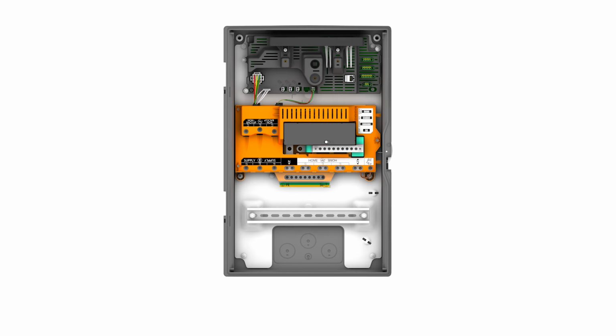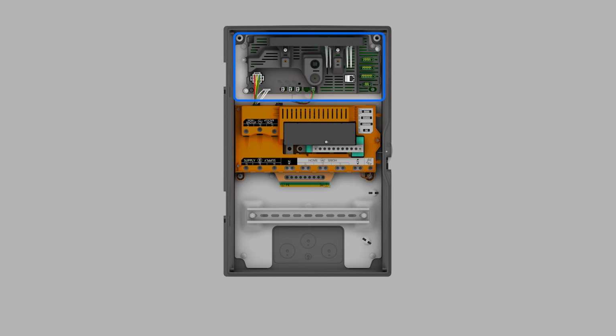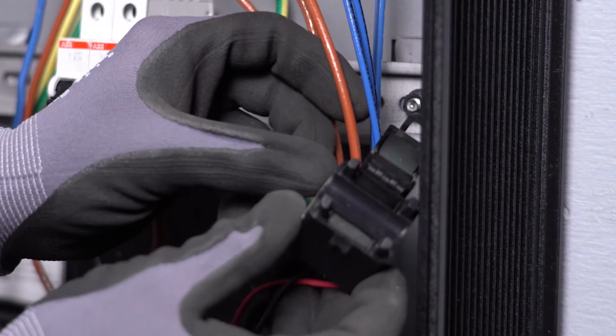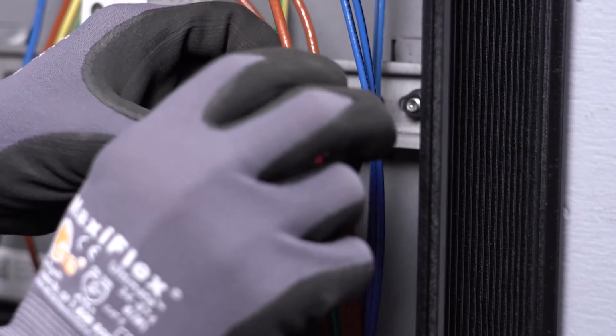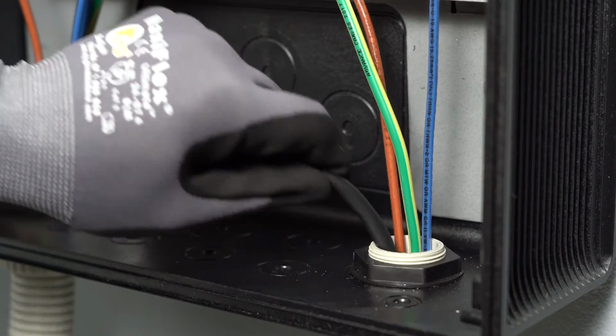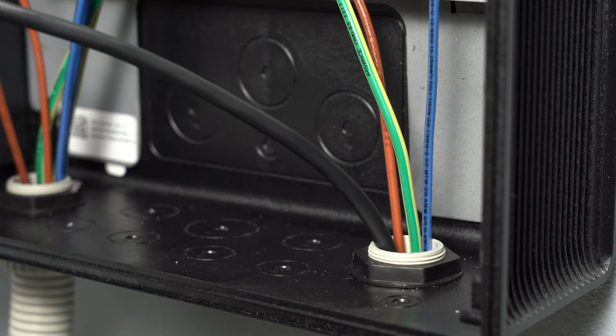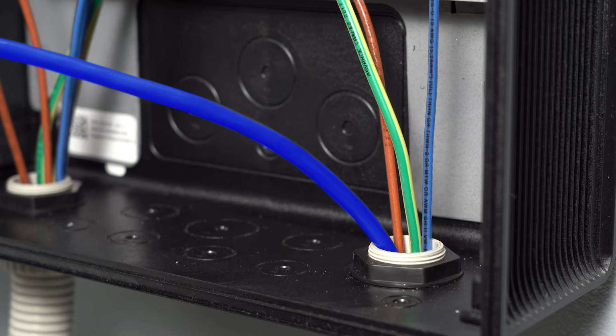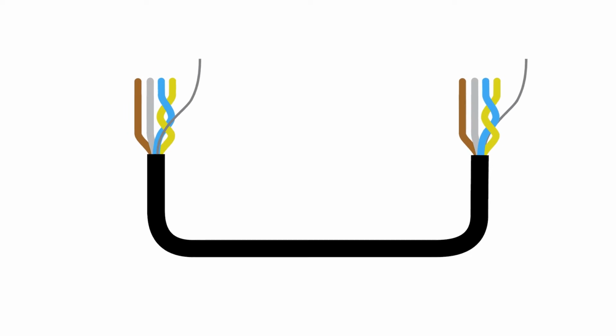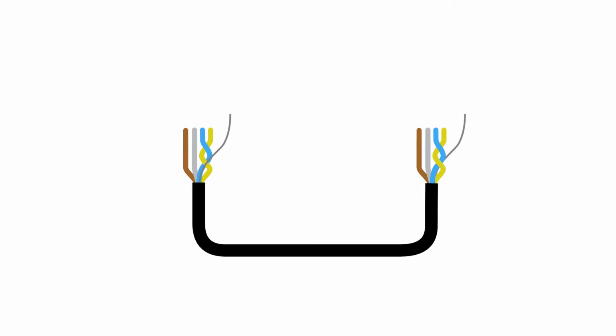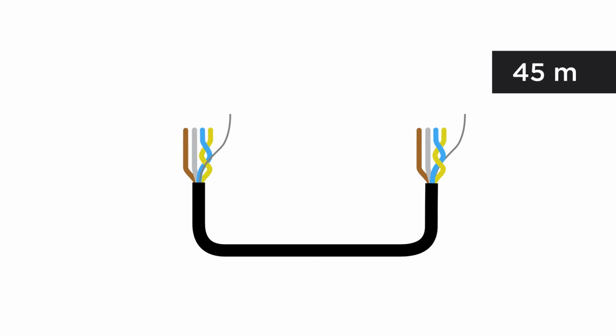The next step is to make the low-voltage connections between Backup Gateway and Powerwall. Energy metering is covered in a separate video. In addition to branch circuit wiring, a communication cable is run between Backup Gateway and Powerwalls. This 4-conductor communication cable should be shielded copper with at least one twisted pair. The cable should be either double insulated or have sufficient voltage rating to comply with local regulations. This cable must not exceed 45 meters in length.